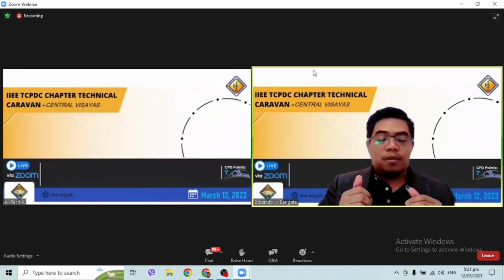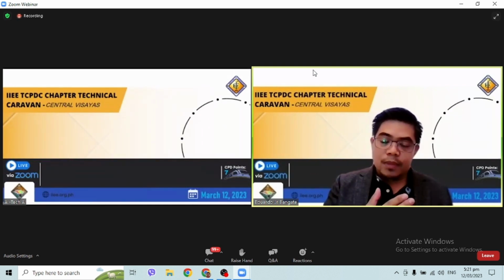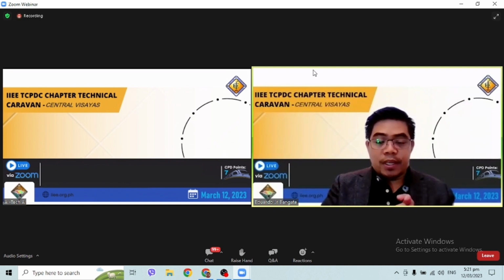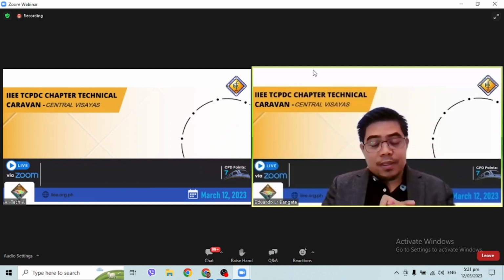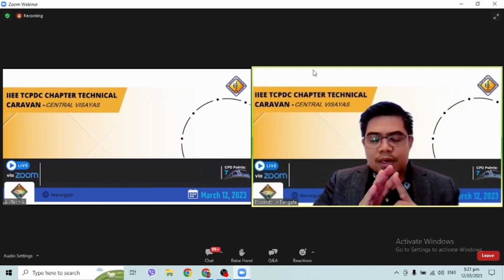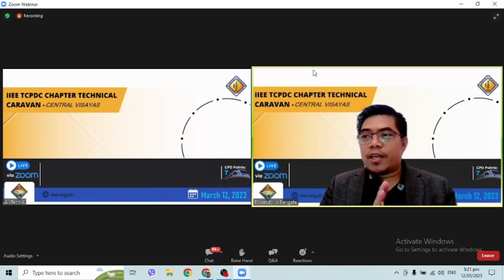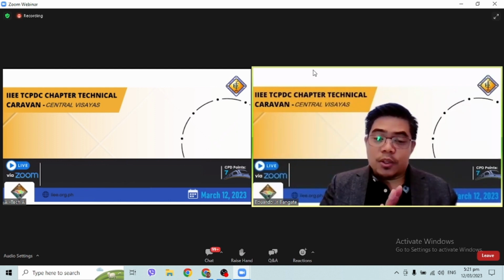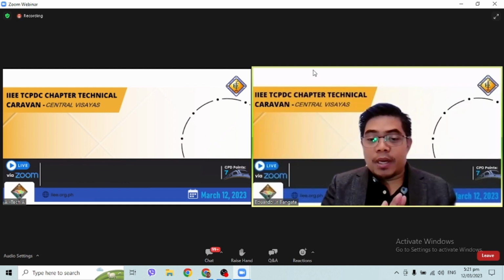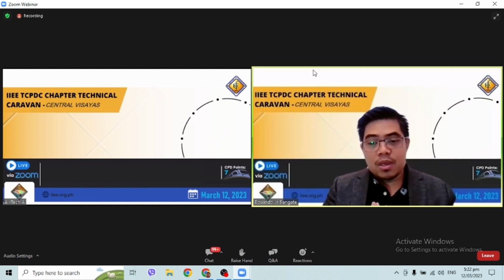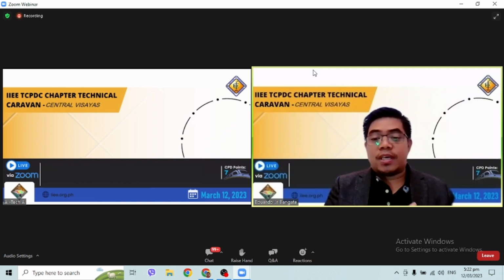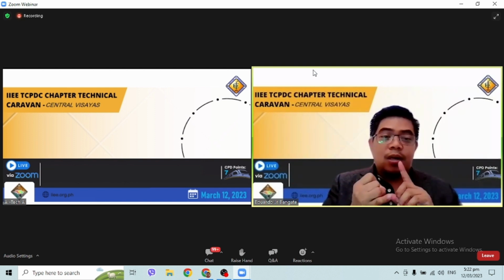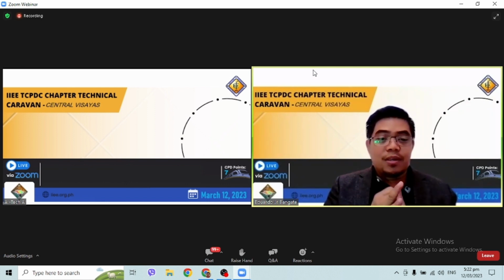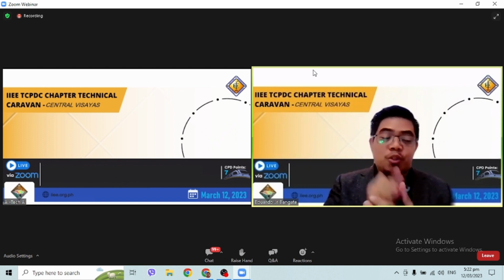But we have to understand that the normal operating level of the generator is 70 to 80% of its capacity. Okay? This is the normal one. Now, ano ibig sabihin nito? Dapat, especially those generators na mga prime power, if your generator is running below 70%, lalong-lalo na below 30% of rated capacity, it will be very, very dangerous sa inyong generator. Meaning the engine is not running at its optimal operating level. It means your engine is not working the way it's supposed to.